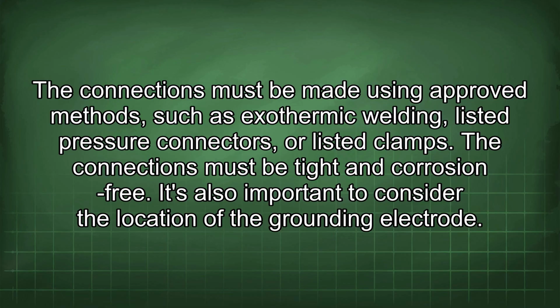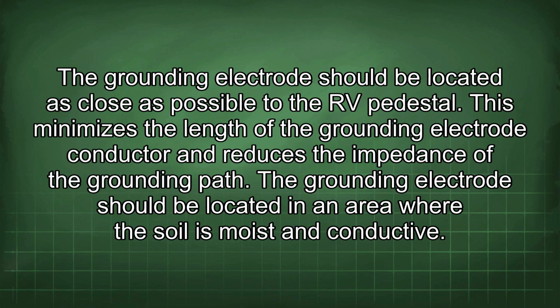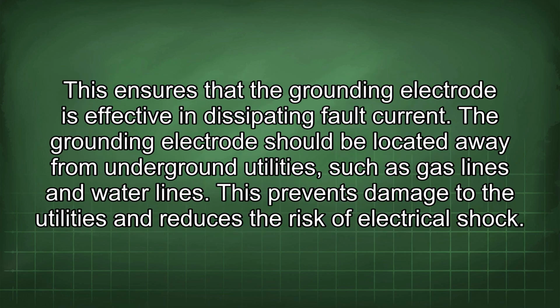It's also important to consider the location of the grounding electrode. The grounding electrode should be located as close as possible to the RV pedestal. This minimizes the length of the grounding electrode conductor and reduces the impedance of the grounding path. The grounding electrode should be located in an area where the soil is moist and conductive. This ensures that the grounding electrode is effective in dissipating fault current. The grounding electrode should be located away from underground utilities, such as gas lines and water lines. This prevents damage to the utilities and reduces the risk of electrical shock.